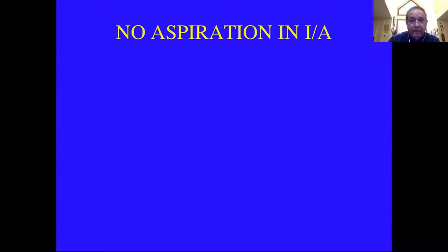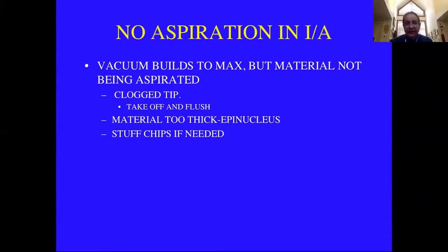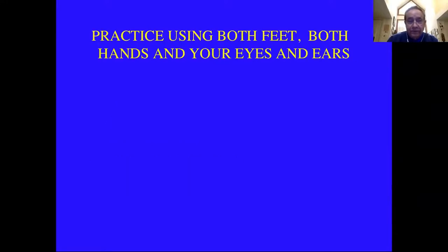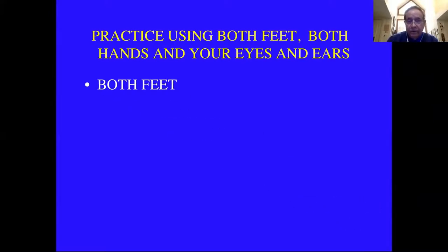If you have maximum vacuum but no aspiration in IA, normally you have a clogged tip which you have to clean off and flush. Sometimes you'll get chips stuck in the opening — you can stuff those in with a second instrument. If your vacuum doesn't build, typically you can have a loose tip or loose aspiration line. You have to practice using both feet, both hands, your eyes, and your ears: one foot for the phaco pedal, one for the microscope; one hand for the phaco tip, one for a second instrument. Watch how things are moving, that you're where you want to be depth-wise and side to side, staying away from the iris. Listen for the sounds of the different functions.